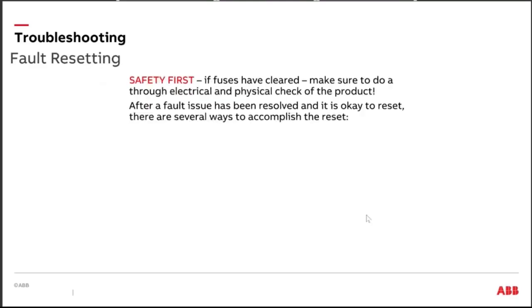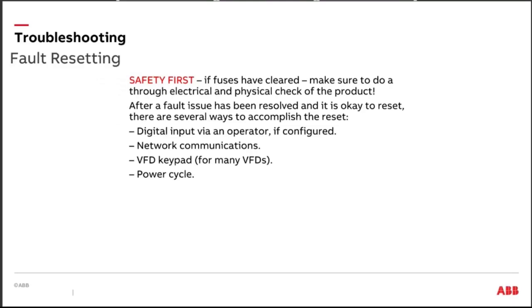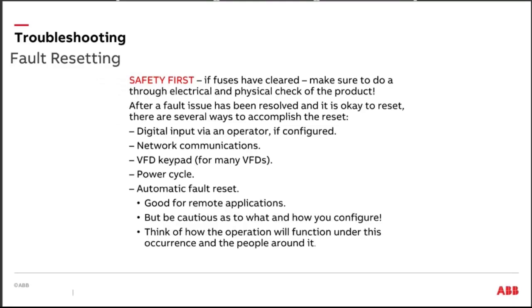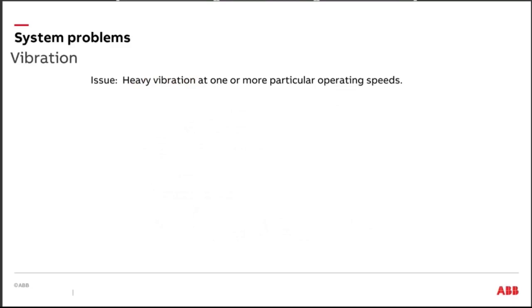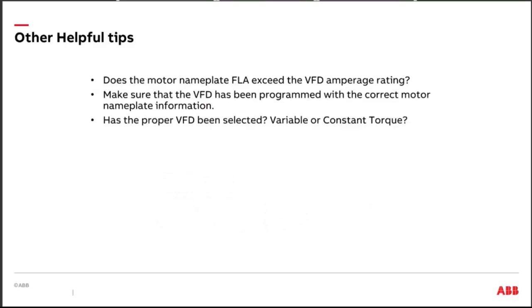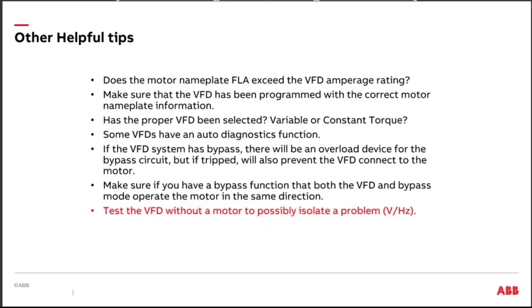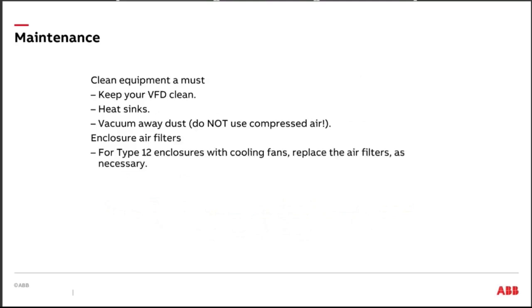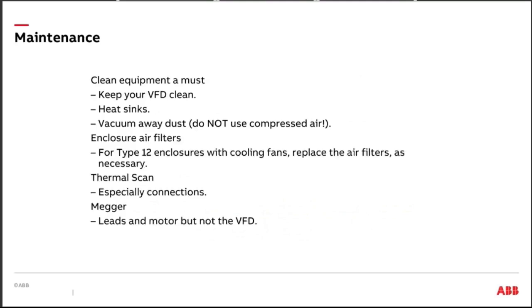Things like that. Resetting a fault, you can have auto reset on a fault. I would always recommend that you mark the drive, that the drive might restart without human intervention. So those are the kind of things that I think about there. There's a lot to look at with the drives, like accelerating too fast, decelerating too fast. So a lot in the setup of the drive. Remember, let's vacuum the drives out. Don't blow the drives out. Let's use type 12 enclosures when we can to keep the nastiness out, and the fan filters go on the output of the drive.